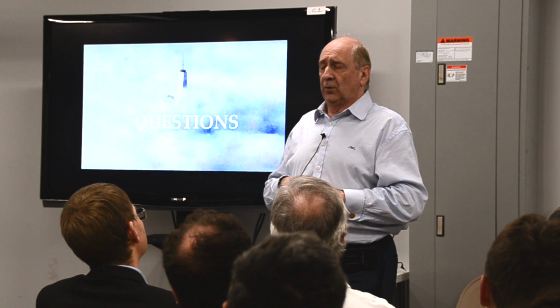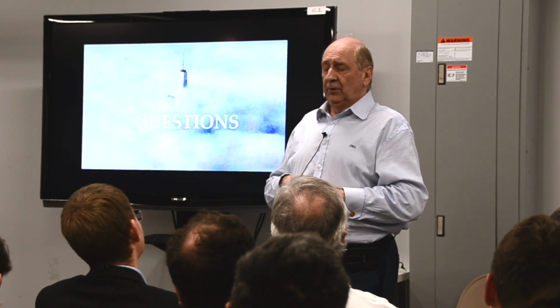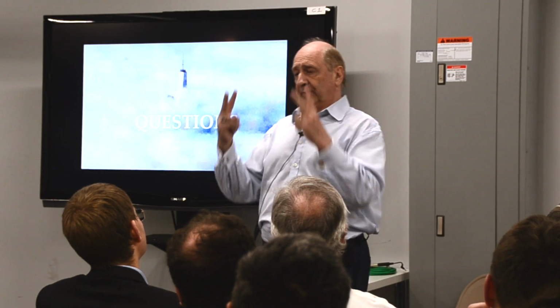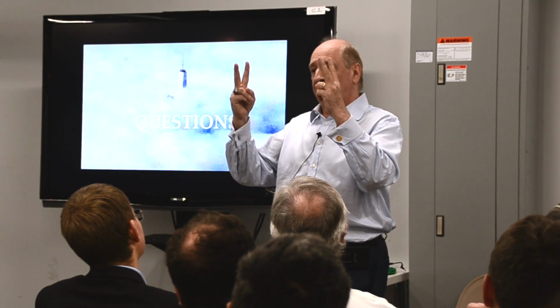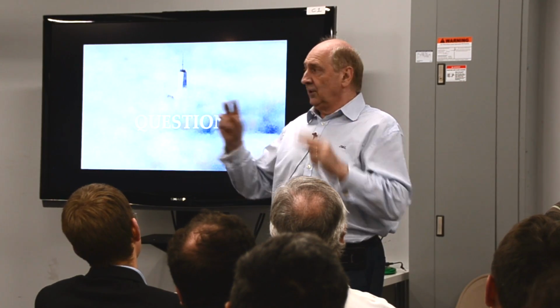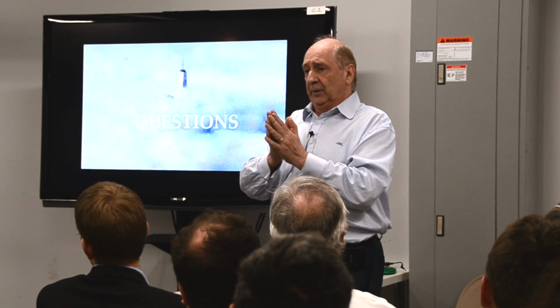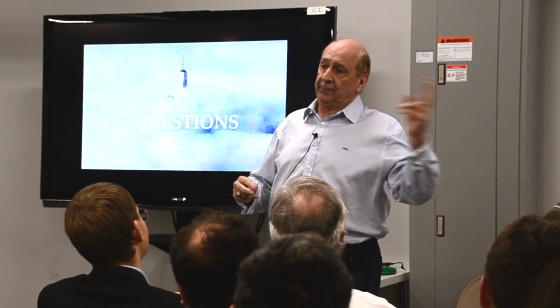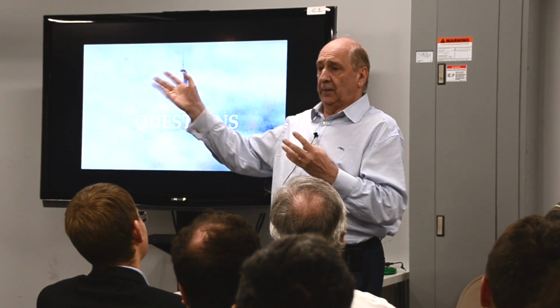What's the backup power like? We have a 2 megawatt generator feeding broadcast. We have 4 PDCs coming in from Con Edison that then come up as 2 feeds to the building to do 2 dual-ended substations at 13.8 kilovolts. We then convert it up here to 480. Generator's 13.8, so we have A, B, or generator. But A and B are also picking up an A and B from the street. So you have 4 coming in, convert to 2 coming up, and the generator, 2 megawatts just for broadcast.